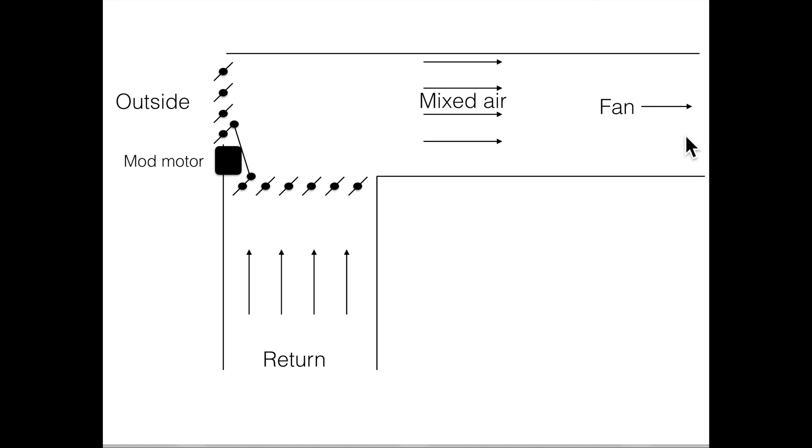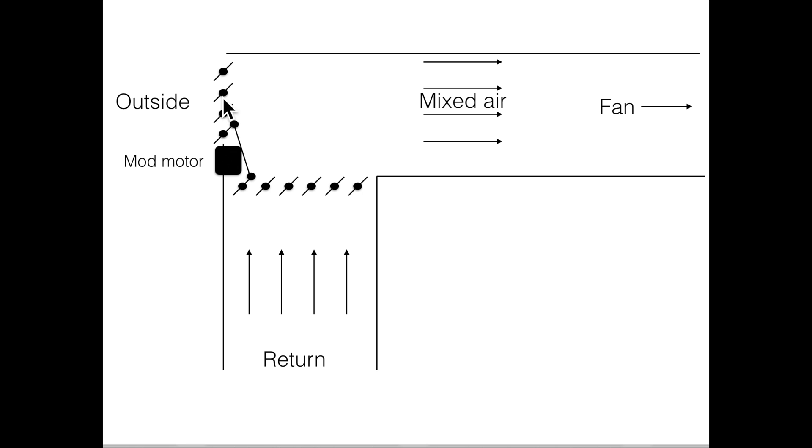This is a return side of the fan. Now because this is a negative pressure here, and it's also a negative pressure here, if these dampers are open, it's going to pull some of the air that moves through here from the outside air.